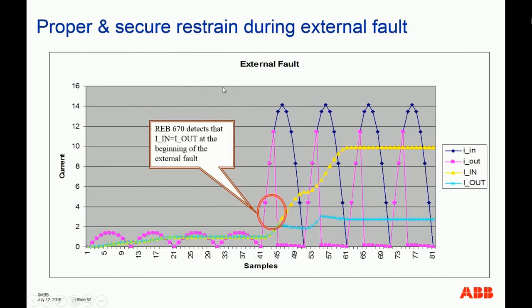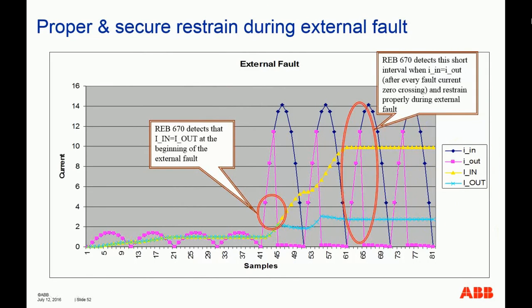Even though the differential current here is above the pickup, it will restrain, because the relay will look at this, detect the in and out currents at the beginning of the external fault, and it knows that they rose together, so it concludes that this is an external fault. Even though there's a significant amount of differential current, it will securely restrain. So this is basically also part of the CT saturation detection algorithm. That's how they look at it. More or less, every vendor has a different way, but all of us are looking at the same thing. They analyze the waveform.